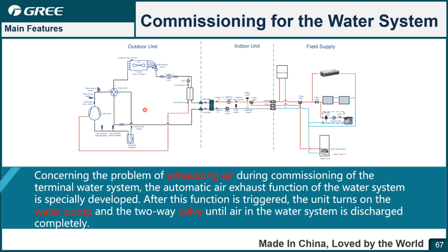And another commissioning function is for the water system. The customer can set this function to exhaust the air inside. In this case, the water pump will start, also the 3-way valve, 2-way valve, and the other valves. All of them will start circulating the water and release the air inside, to make sure there is no air in the water system and the running pressure is stable.